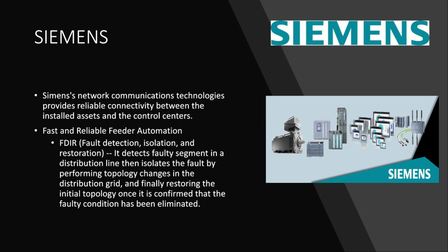They're also using FDIR, which stands for fault detection, isolation, and restoration. It detects a fault segment in a distribution line, isolates the fault by performing topology changes in the distribution grid, and finally restores the initial topology once the fault condition has been confirmed eliminated.